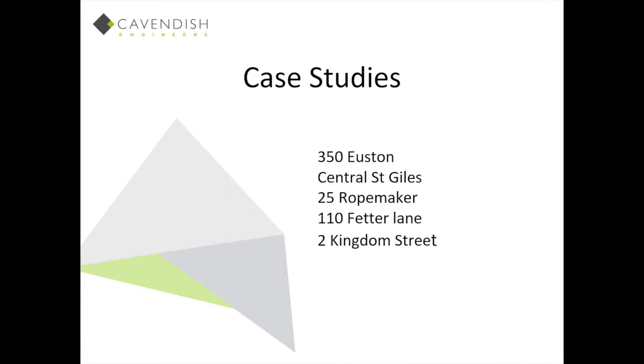Central St Giles, a large building you may have seen on Tottenham Court Road, multicoloured. We're using the condenser water from the chillers there into a heat pump so that no heating is required. Because the client requires both heating and cooling, we get 365 days of heating and cooling with no gas.